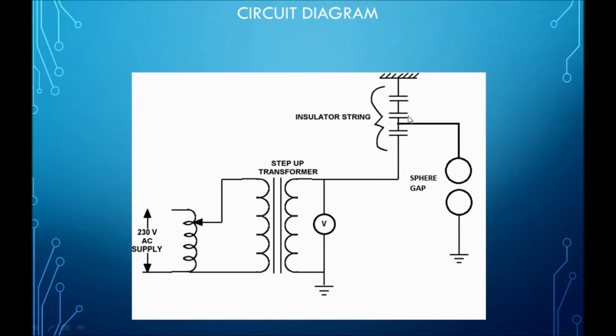And this is the ground terminal. You can see the spark gap. This is the spark gap unit. The spark gap is connected to this point, and the other sphere is connected to ground. Then the spark gap acts as a voltmeter. Which units does the spark gap measure the voltage across? These two units, because this is a ground terminal and this is also a ground terminal. So the spark gap measures the voltage across these two insulators.